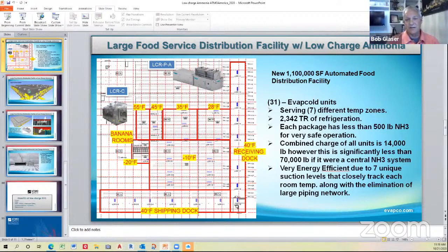The nice thing about this is, you think about 2,300 tons of refrigeration, and we don't have any package that's got more than about 475 pounds of ammonia in it. So if we have some terrible problem and lose 475 pounds, and it's 80 feet in the air, we're able to send that into the atmosphere. It's just a huge load off of the maintenance and safety guys and everything else.